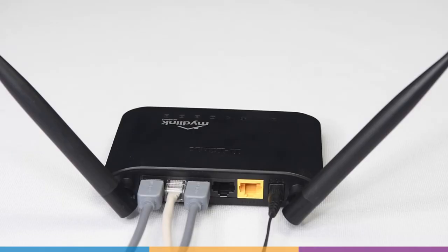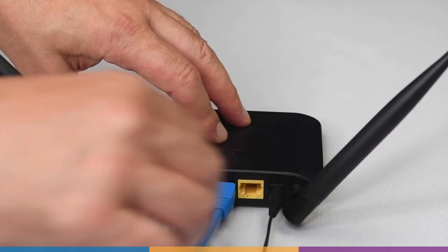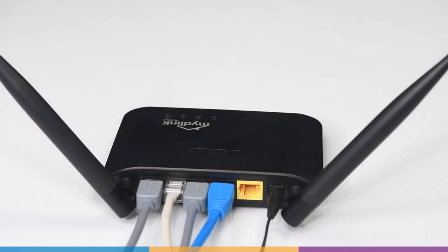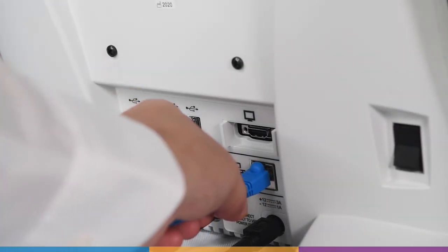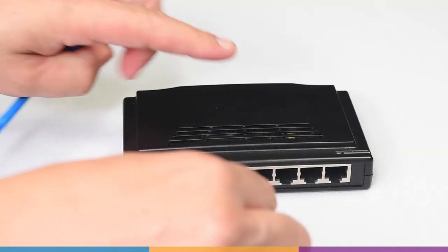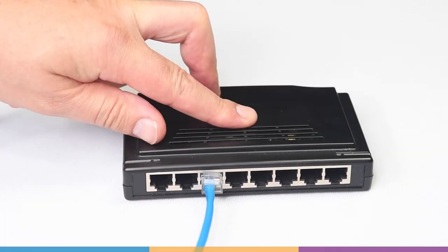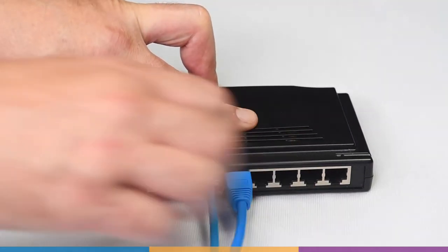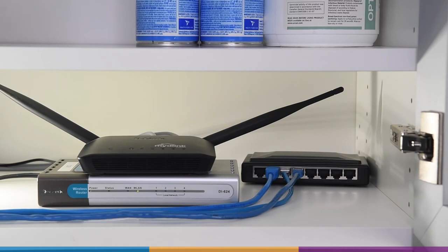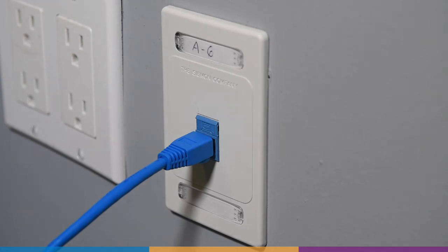If you wish to use a wired connection, the simplest method is to connect an Ethernet cable to an empty port in the router, then to the back of the Verifit. If the router's ports are all in use, you can create more connections by adding a device known as a network switch. In a slightly more sophisticated setup, the router can be hidden away in a closet and the connection run through the building to an Ethernet jack in a wall plate.